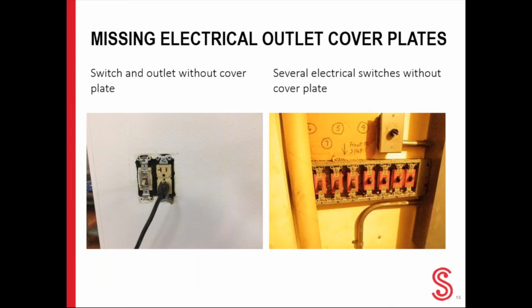Switch cover plates and receptacle cover plates are designed to prevent people from coming into contact or touching properly installed live electrical parts that are inside the switch receptacle box. When the live parts inside the box are properly installed and the cover plate is on, those parts will not be normally exposed to human contact.